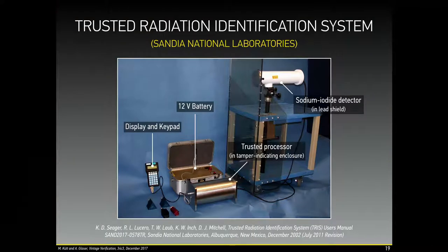It's based on a template approach, so it measures a sample and then compares this to an item you want to inspect. For this, it uses a simple sodium iodide detector, a radiation detector that detects gamma rays. It's very rough in the spectrum it generates, but it's good enough for the purpose.